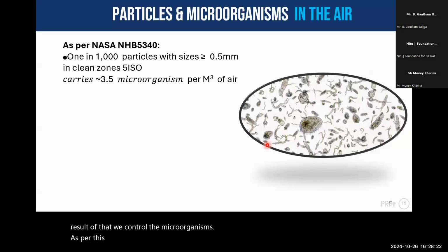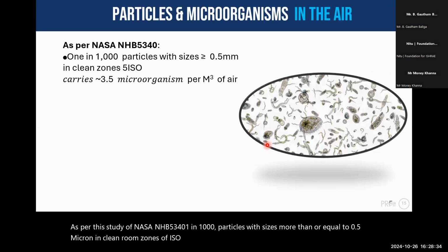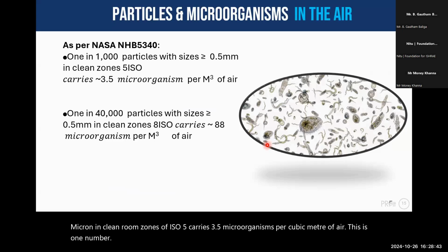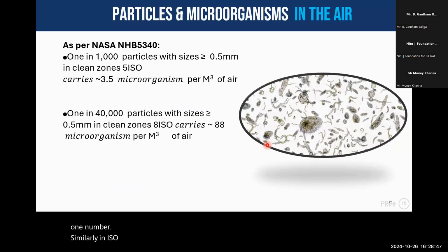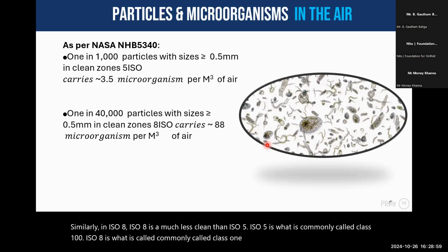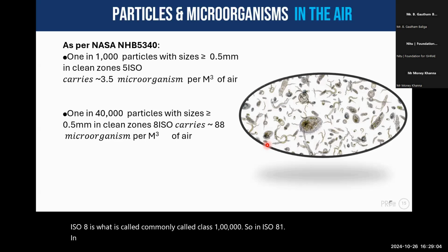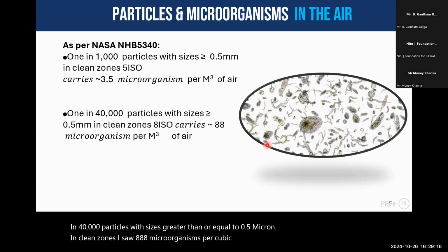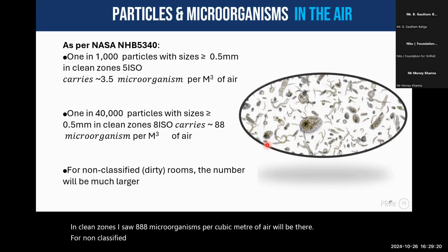As per this study of NASA NHB 5340, 1 in 1000 particles with sizes more than or equal to 0.5 micron in clean room zones of ISO 5 carries 3.5 microorganisms per cubic meter of air. This is one number. Similarly, ISO 8 is much less clean than ISO 5. ISO 5 is what is commonly called a class 100. ISO 8 is what is commonly called class 1 lakh. So in ISO 8, of 1 in 40,000 particles with sizes greater than or equal to 0.5 micron in clean zones, 88 microorganisms per cubic meter of air will be there. For non-classified dirty rooms, the number will be much larger.